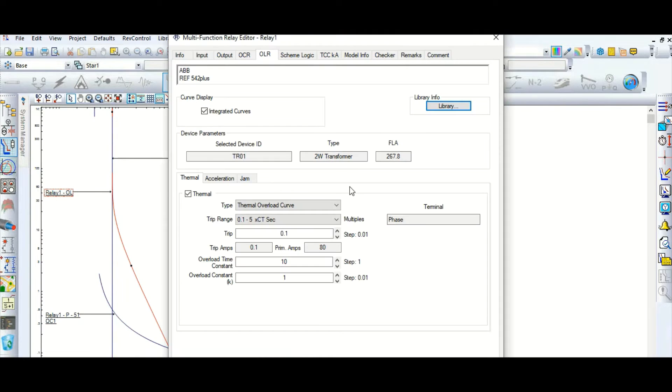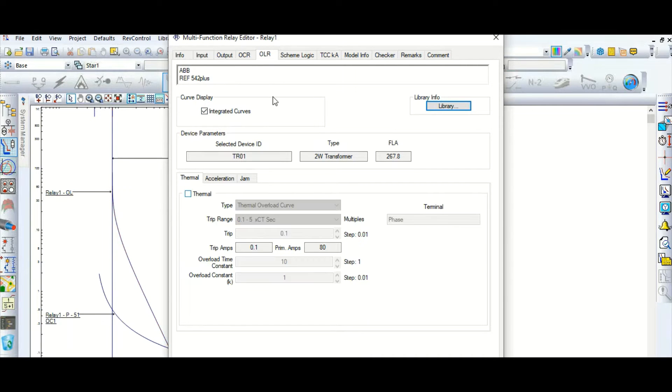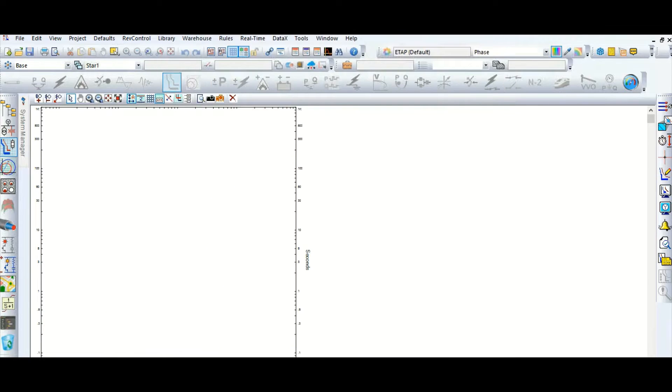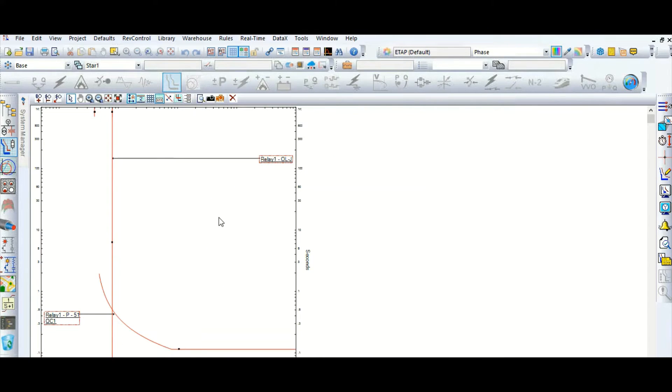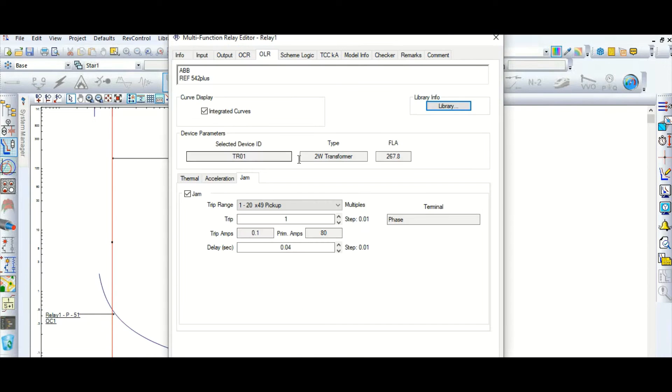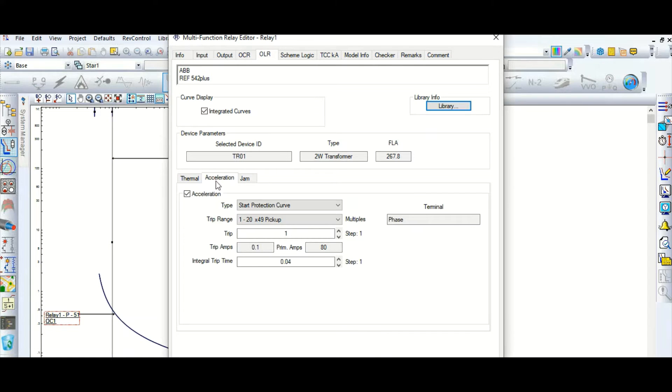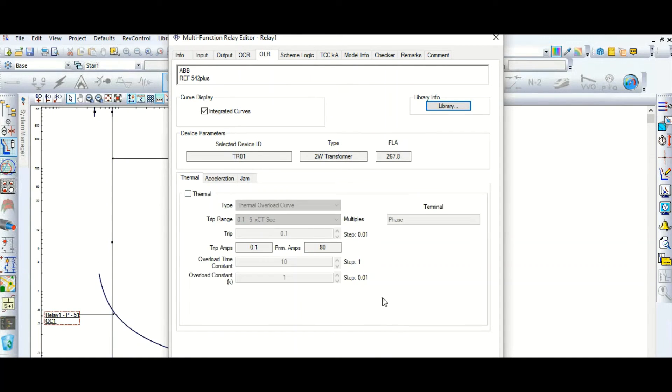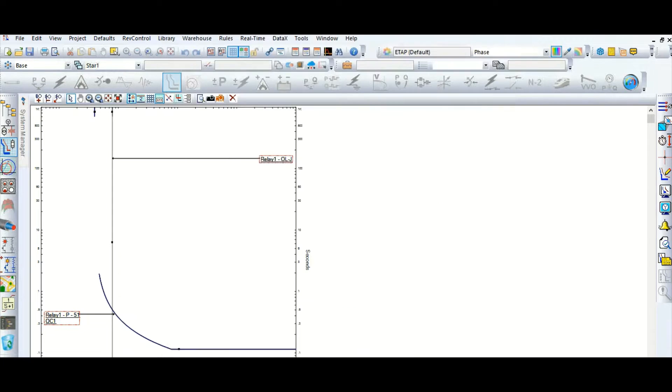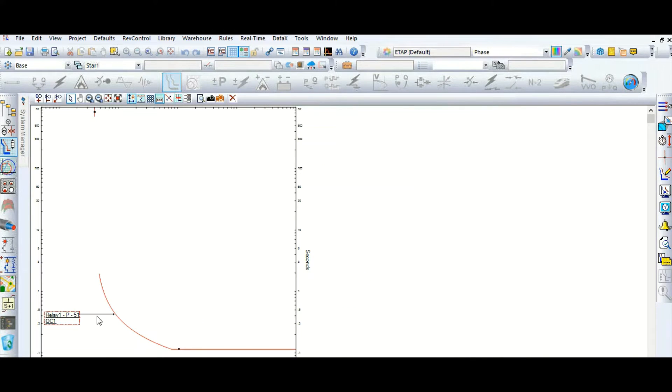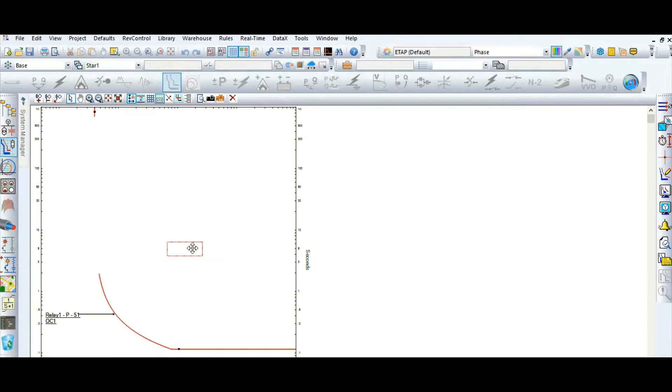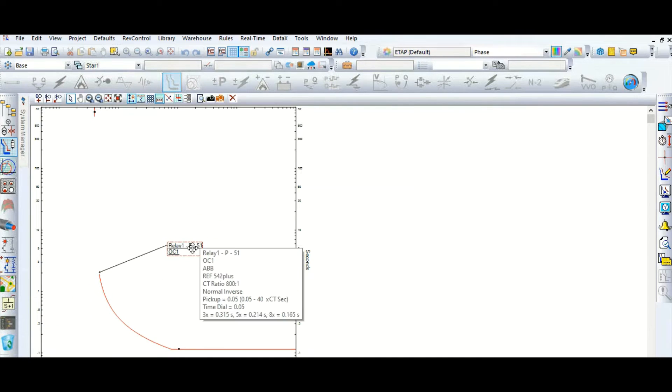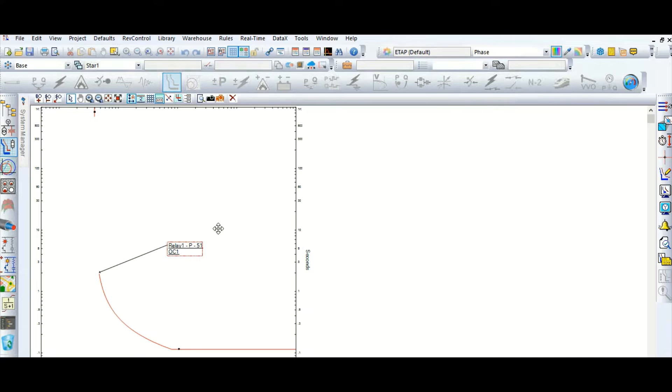Okay, now let's switch off the thermal element, thermal overload. I am not discussing about the thermal overload now, okay. This one also, jam acceleration. So the thermal also I have disabled. Only I will talk about this 51, about this 51 relay element.